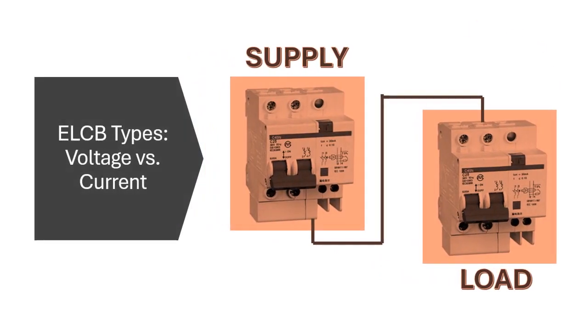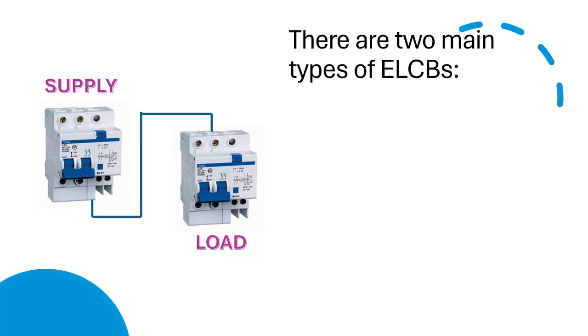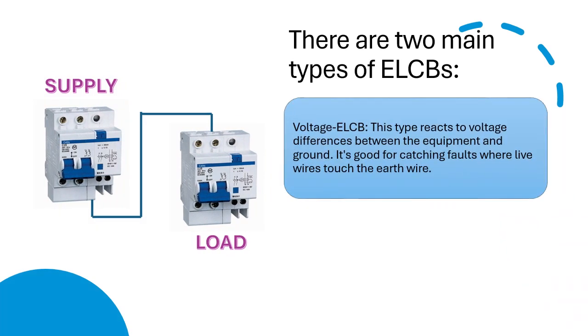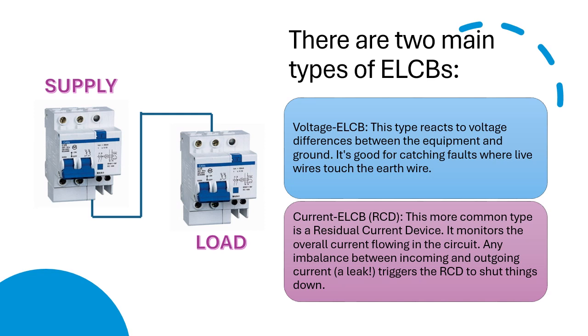ELCB types: voltage versus current. There are two main types of ELCBs. Voltage ELCB reacts to voltage differences between the equipment and ground, and is good for catching faults where live wires touch the earth wire. Current ELCB, or RCD, is the more common type, a residual current device. It monitors the overall current flowing in the circuit, and any imbalance between incoming and outgoing current, a leak, triggers the RCD to shut things down.